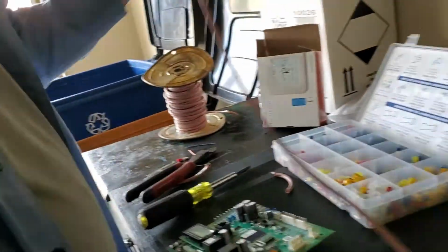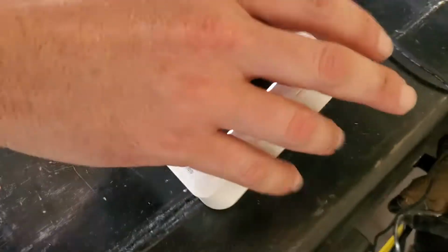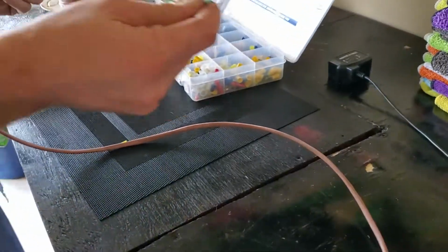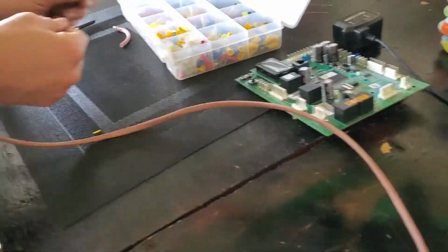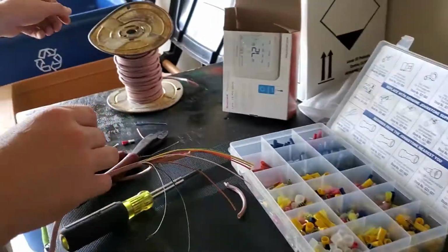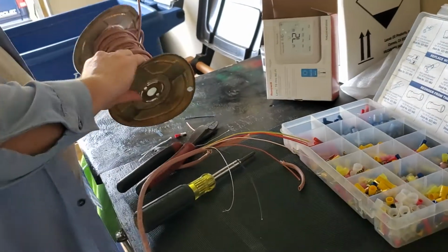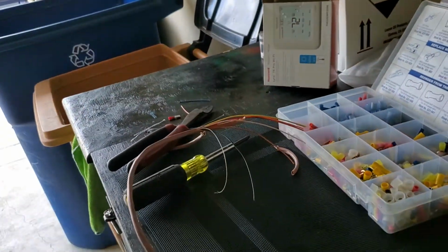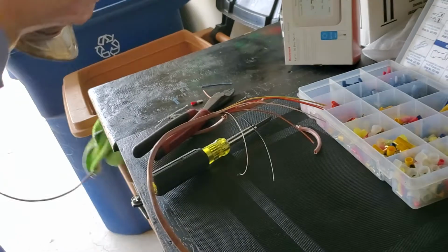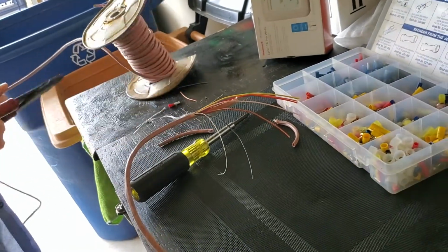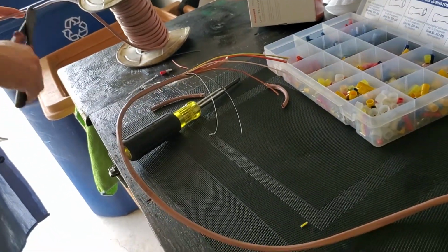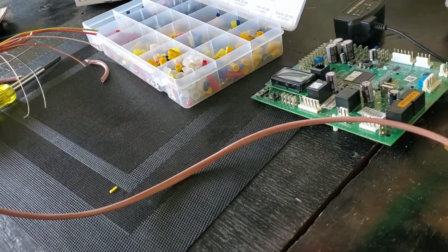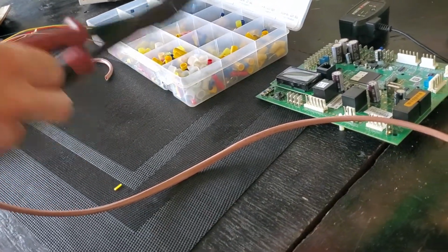So this is your basic connection. This is your thermostat on the wall, and this is your control board up in your air handler. The thing you're looking for with the control board in the air handler is it's going to have two sets of wires - the wires from the thermostat to the control board in the air handler, and the wires from the air handler to the condenser.